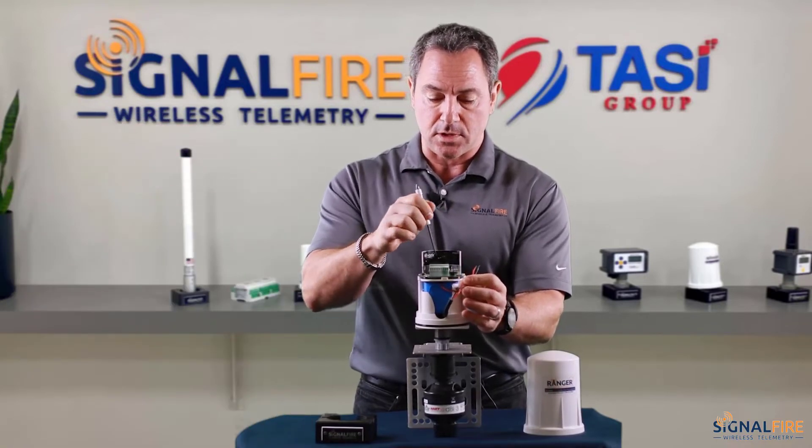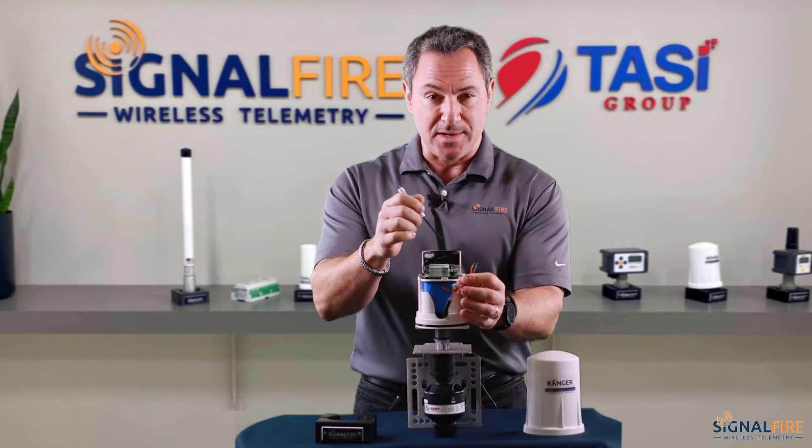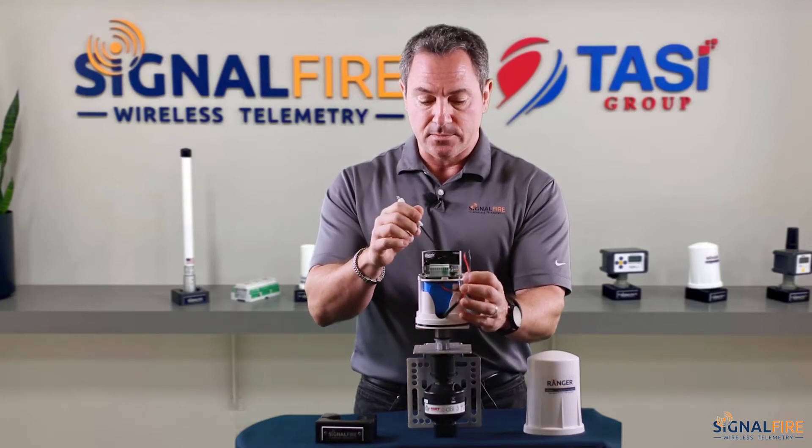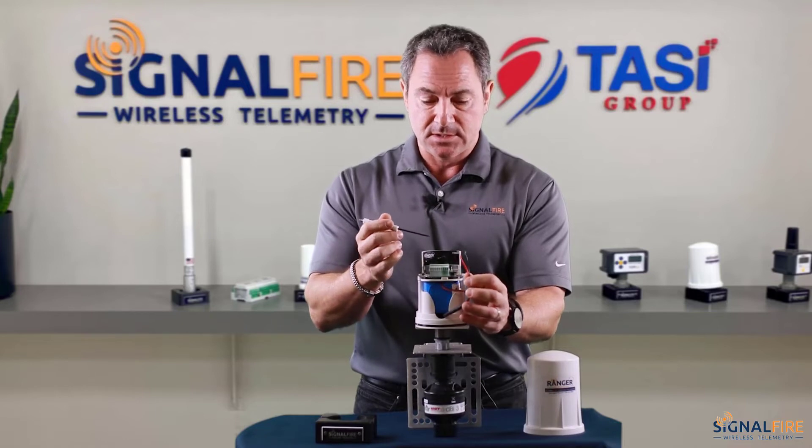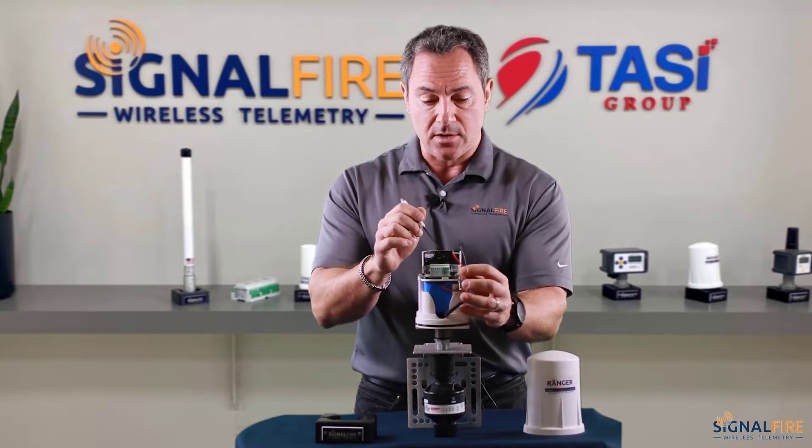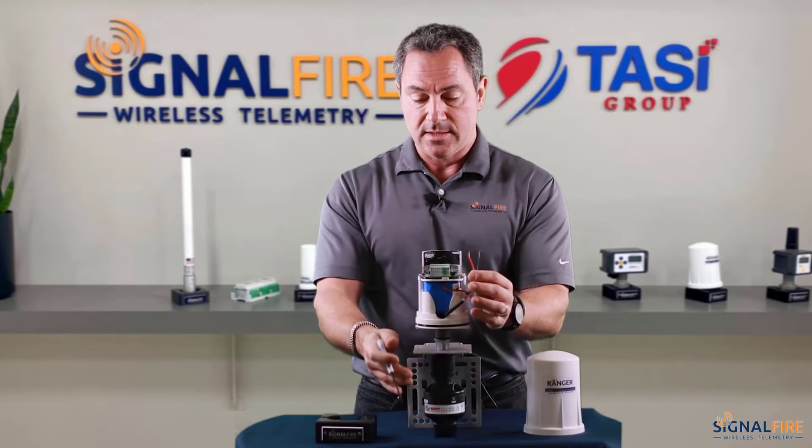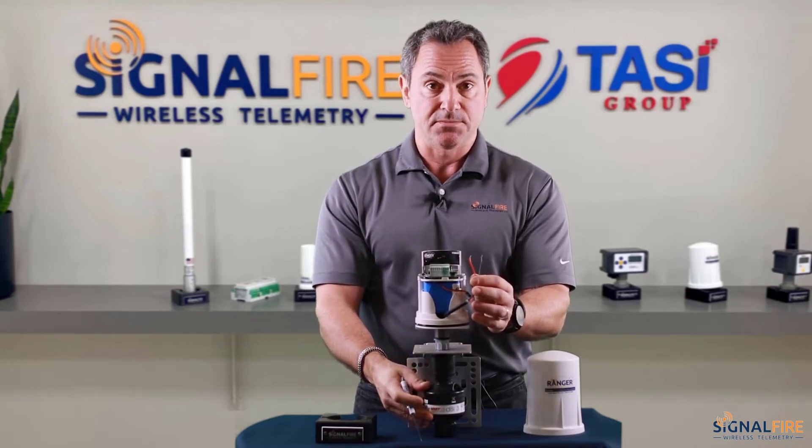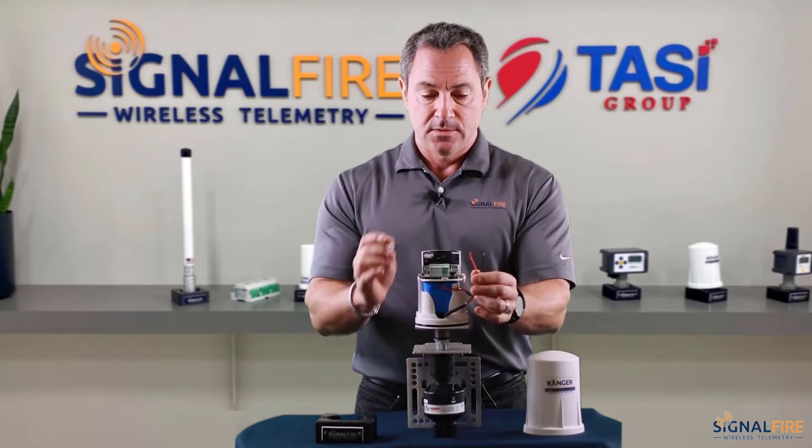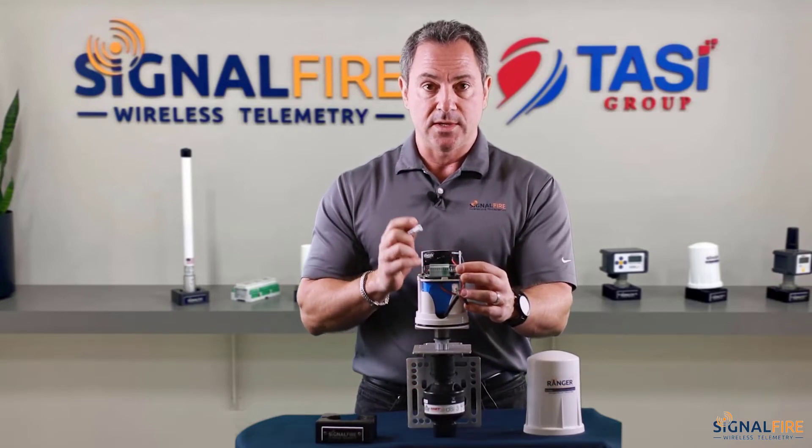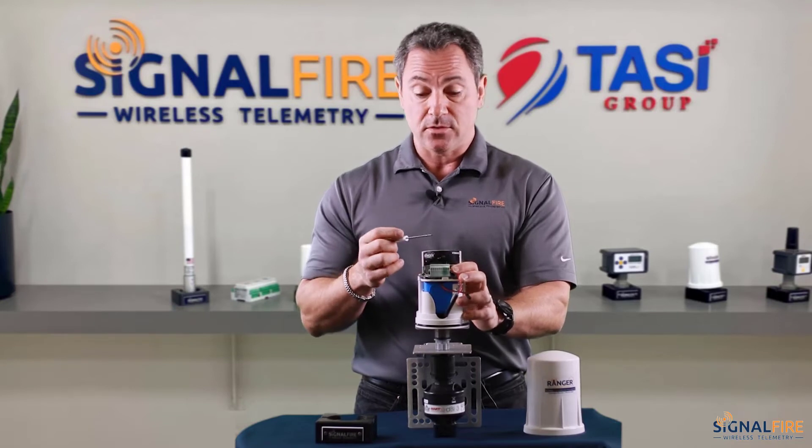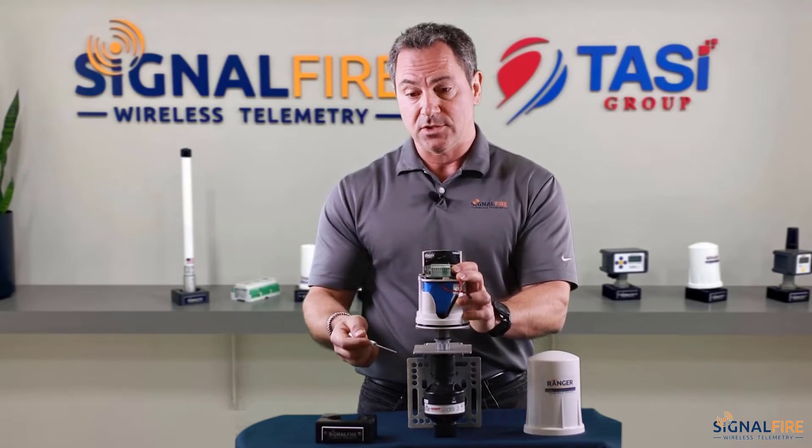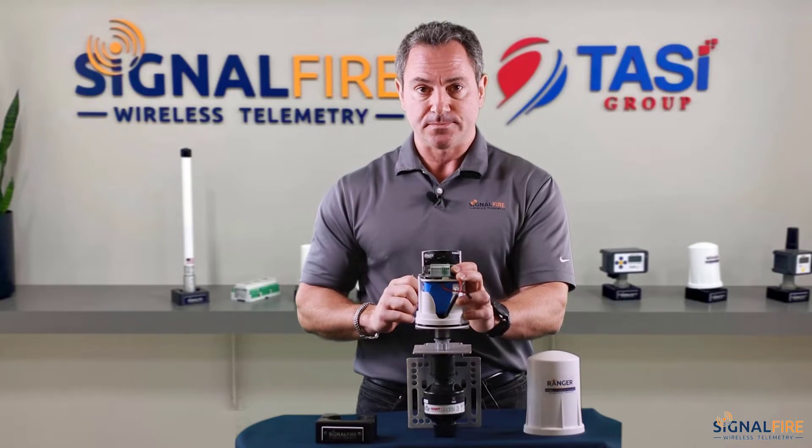We call those daughter cards the multitude of expansion cards that we offer. You can have HART, Modbus, SDI-12. In this case, I'm using a HART interface card that will interface with the HART values and measurements coming from this Pulsar sensor. Once you land those two wires, we can then move on and configure the Ranger to power and measure the Pulsar sensor. Let's move on to the web app right now to fully configure it.